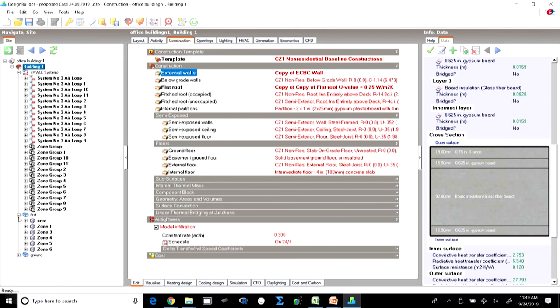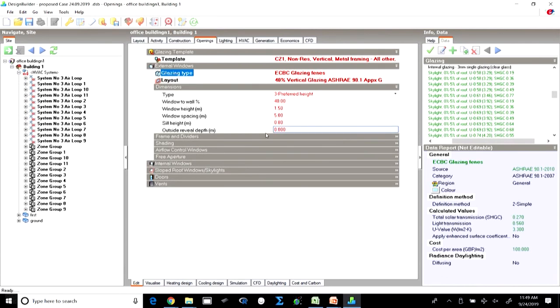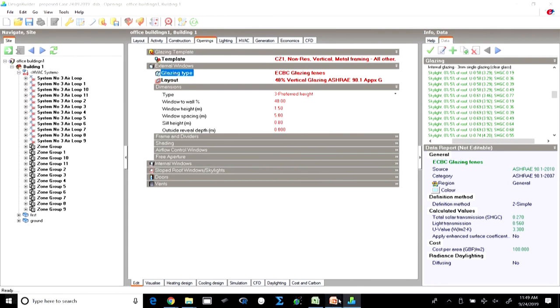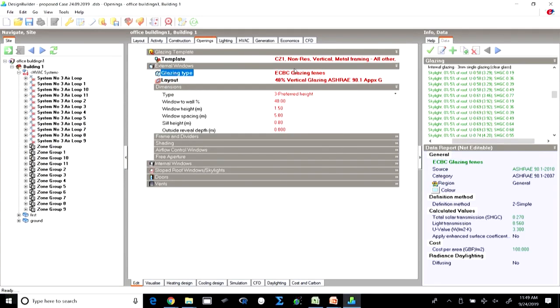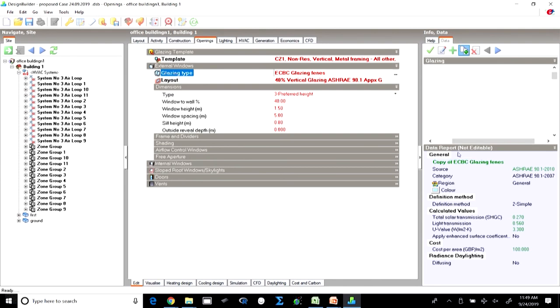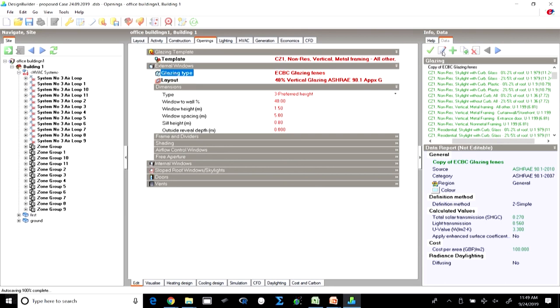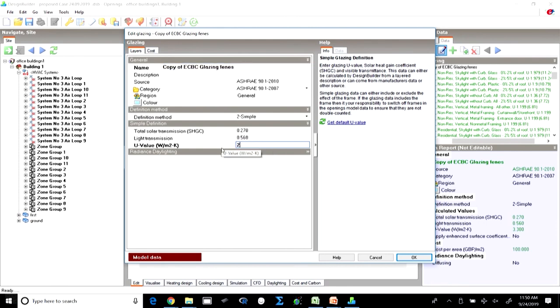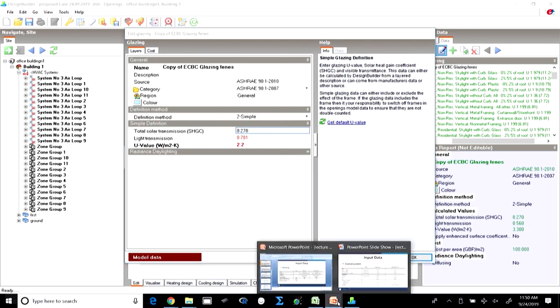This is automatically reflected in both floors. Then we move on to openings. The change in openings involves changing the glass in the proposed building. We change it to the new glass whose properties are being shown here. Instead of using the ECBC glazing fenestration, we create a copy and edit the properties. Instead of 0.27, the solar heat gain coefficient has been proposed to be 0.25, the U-value to be 2.2, and the VLT to be 0.78. The light transmission becomes 0.781 and the SHGC goes to 0.25.